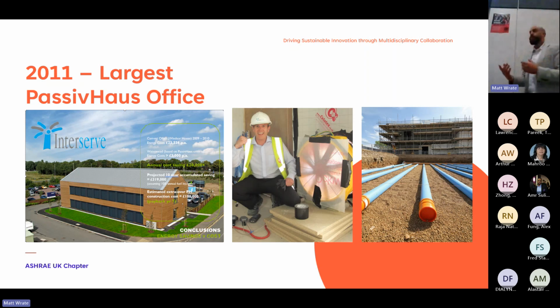We were quite cautious about this, as a designer you tend to be over cautious, and the manufacturers were claiming around an 8-degree rise. We designed in 6, but in reality it was delivering more like a 10-degree rise. So it would be 32 outside and you could get 22 coming into the building, which is really remarkable. It was actually a really good system, albeit quite expensive. That project had a really interesting innovation side to it, and a very willing client that made it work.